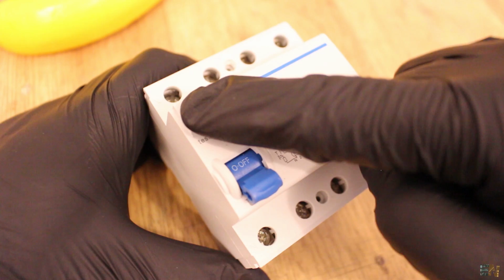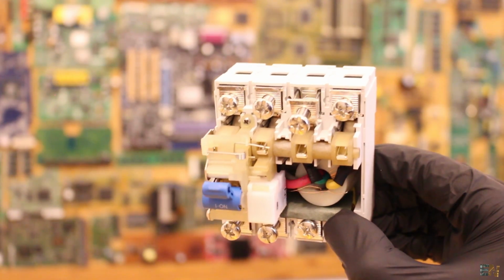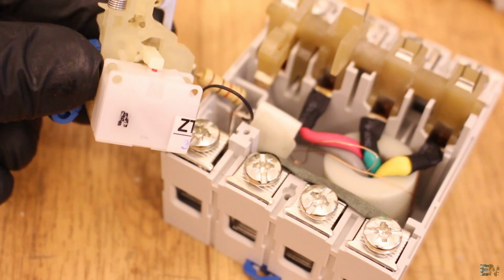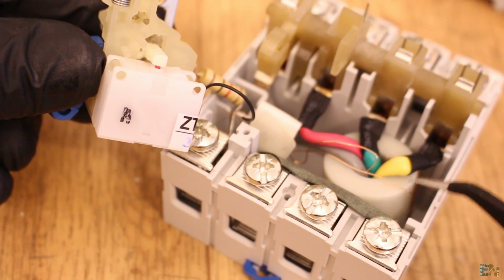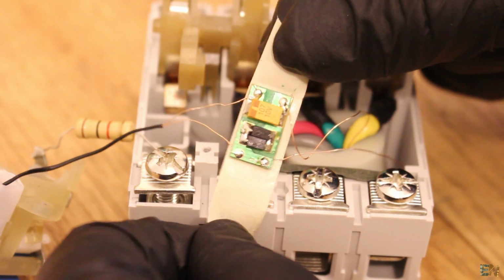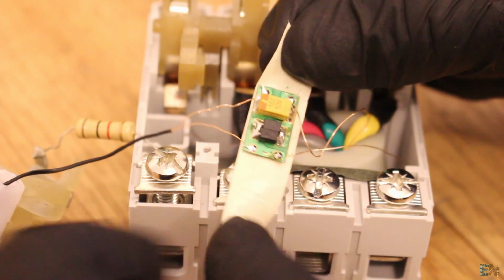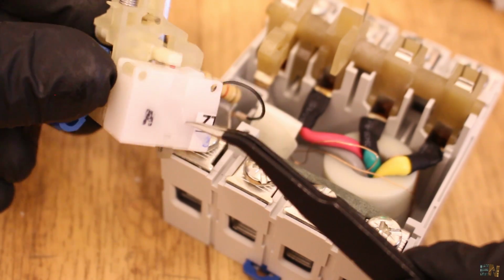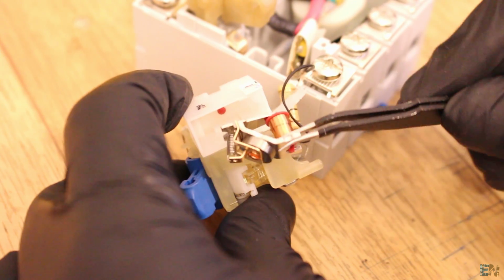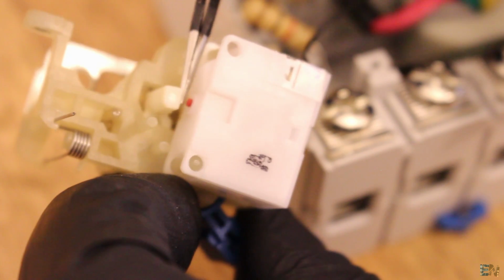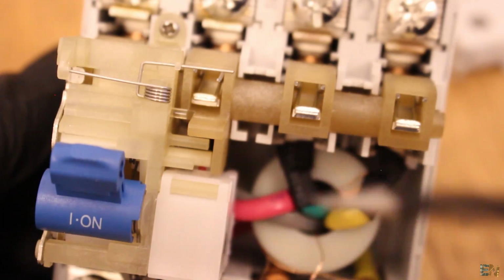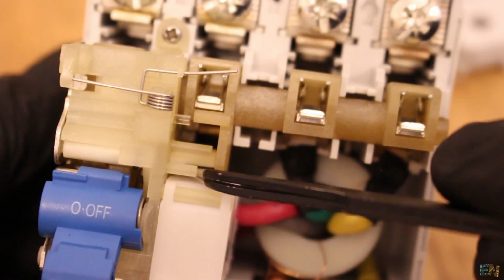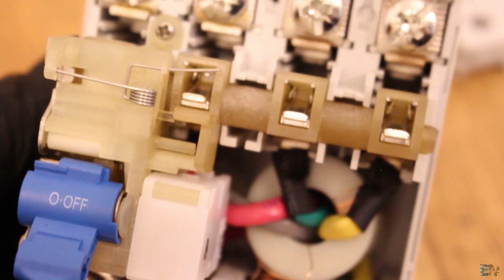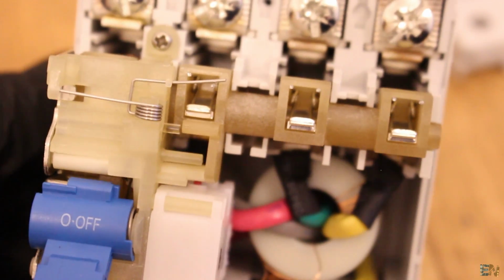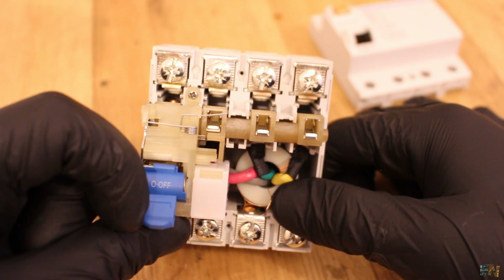The rest of the components are just the terminals for the neutral and live wires 1, 2 and 3. The magnetic field from the transformer induces a small current, that is rectified with this small rectifier. And inside this white case, we have another coil as a relay. This coil will push this red piston, and that will trigger the switch and interrupt the circuit. When the RCCB jumps, all connectors will separate from the terminals as you can see. And the circuit is now open and we are protected.